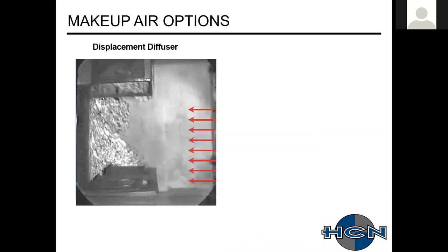So the first one up here is the displacement diffusers. They found this to be pretty analogous to using transfer air. So supplying makeup air through the diffusers at a good distance away from the hood was a pretty effective strategy for introducing the air.